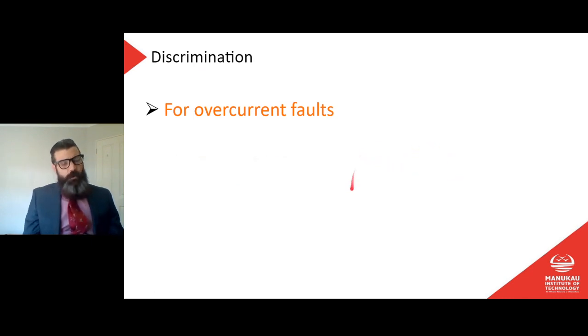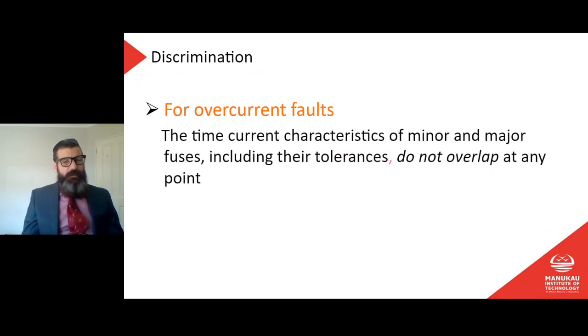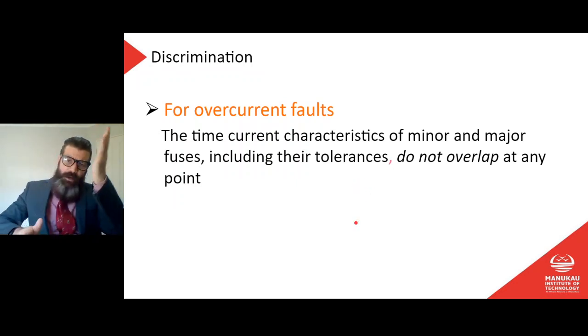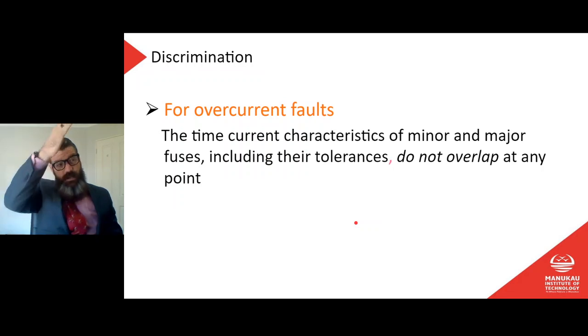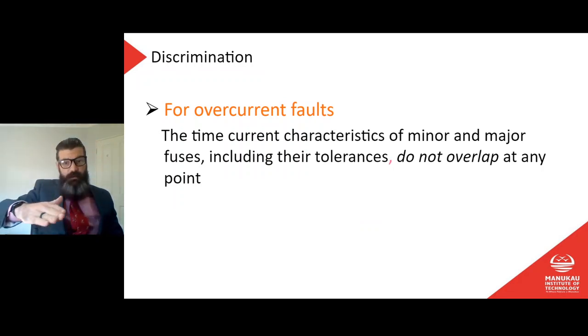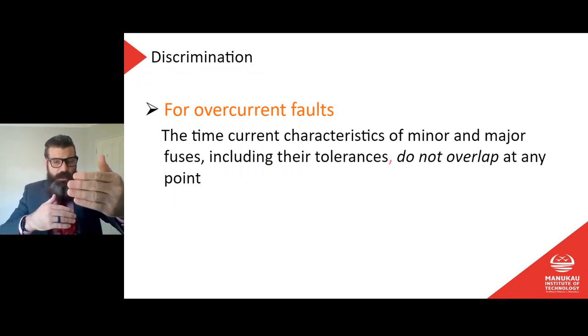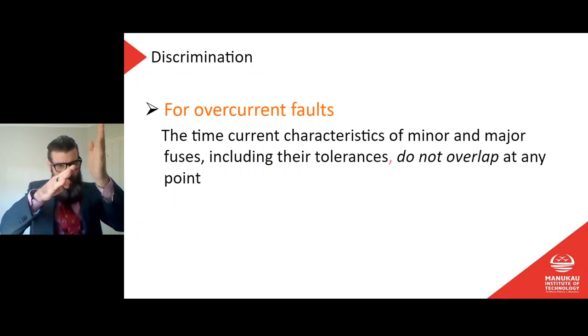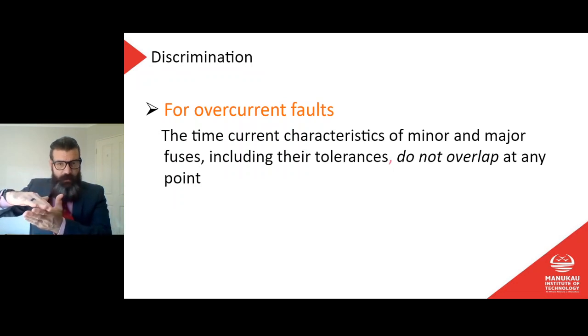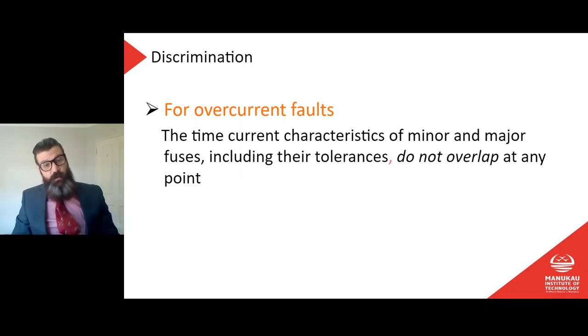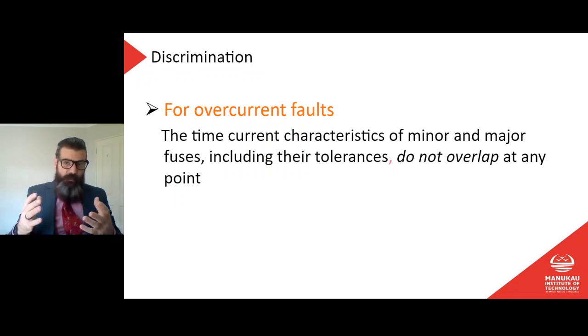Okay, discrimination for overcurrent faults. So that previous one is for short circuit faults, but for overcurrent faults, the time current characteristics of minor and major fuses, including their tolerances, do not overlap at any point. What does that mean? So remember, our time current characteristic means that as our current rises, our time taken to trip decreases. Now, if we have two fuses, one ahead of the other, and the time current characteristics overlap at any point, that means that at some point, as the current goes up, the bigger fuse is going to trip before the smaller fuse, which again is pointless. We don't want that at all. We always want that smaller one to trip if possible.